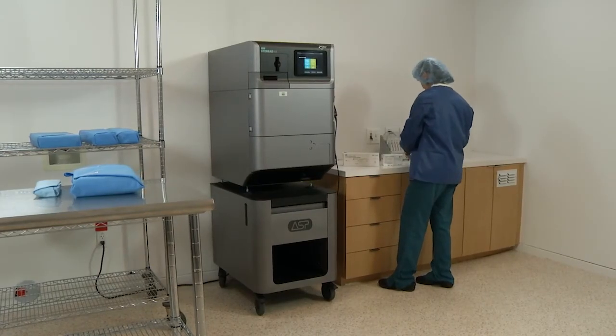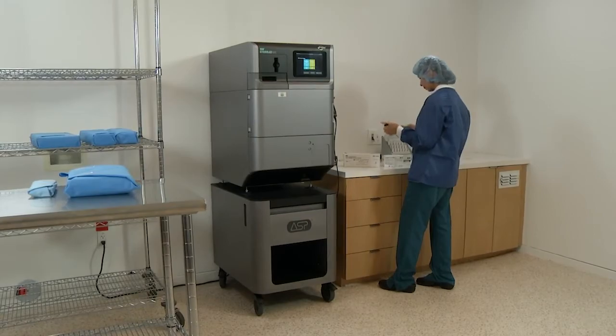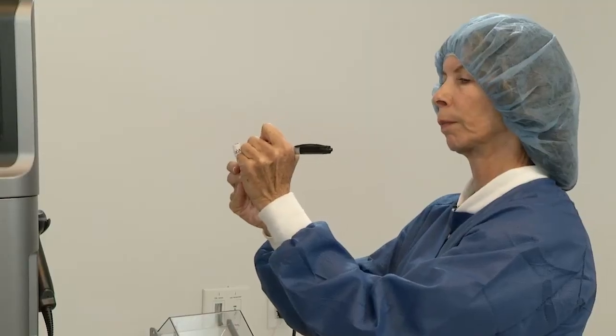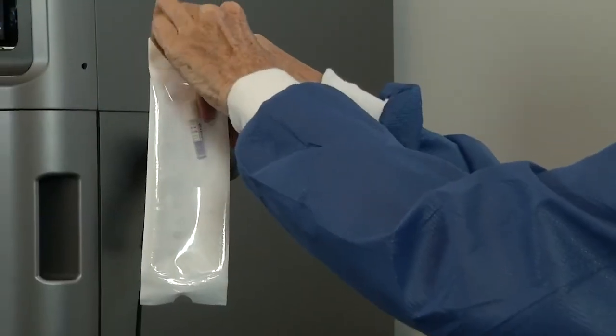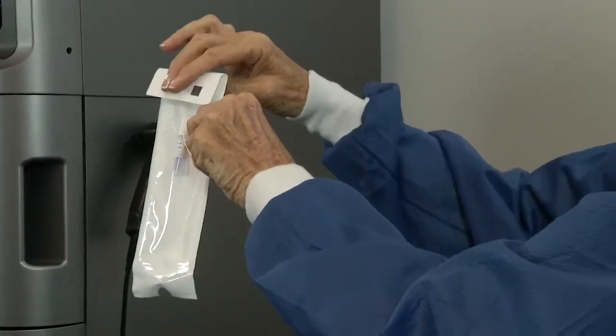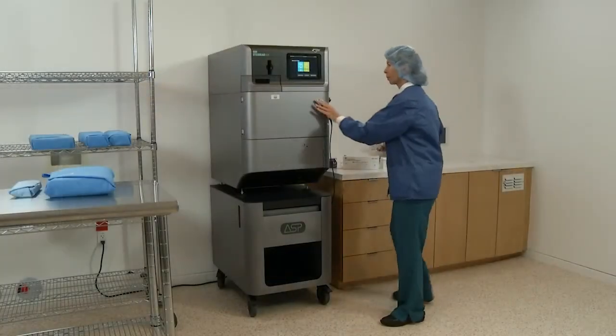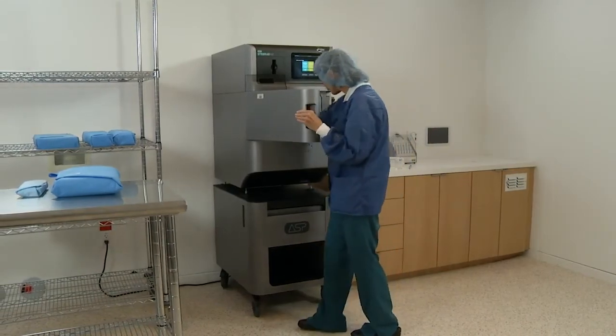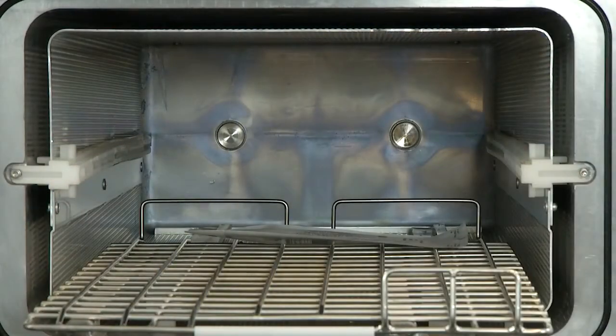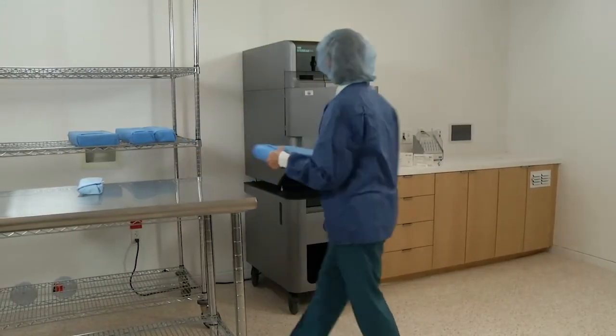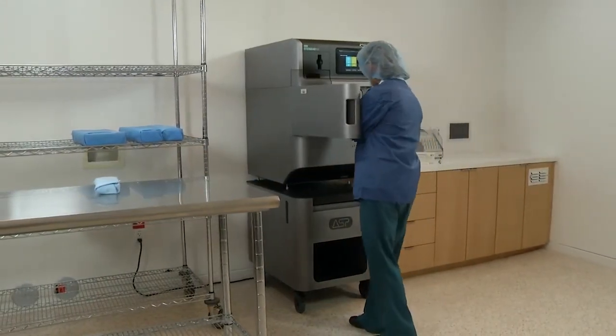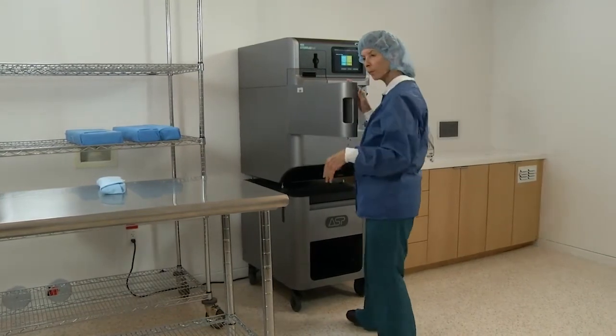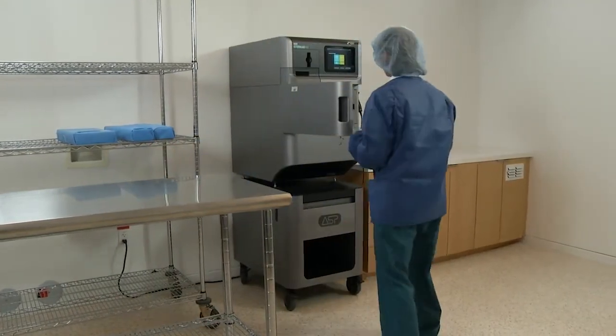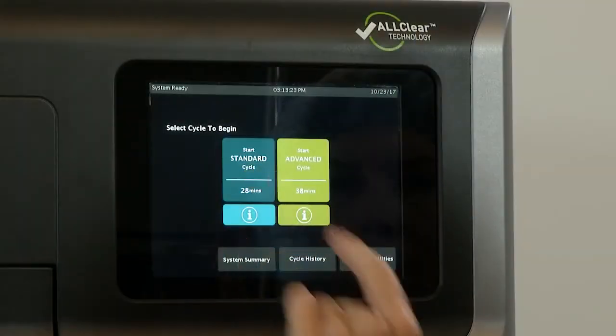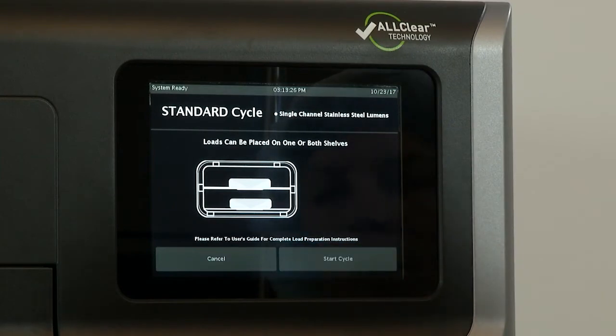Step 2. Label the unprocessed BI vial with a marker, writing the load number and date in the designated area. Step 3. Place the BI in a Tyvek pouch and place the pouch on the lowest shelf close to the rear of the sterilizer as indicated on the sterilizer screen. Step 4. Place the load in the sterilizer. Initiate the desired sterilization cycle and wait for the process to finish.